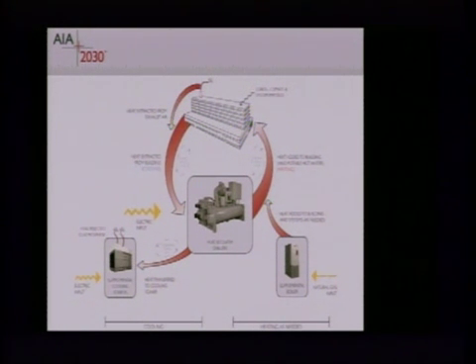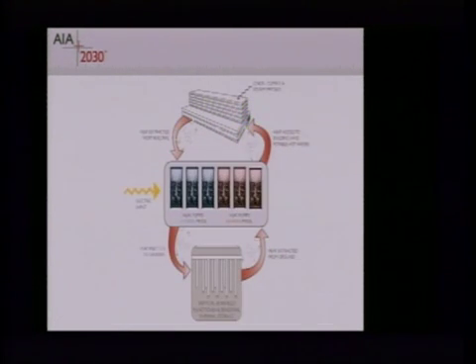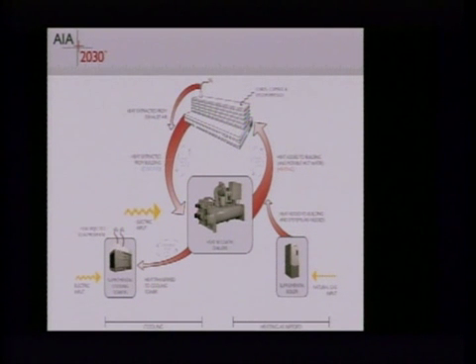And remember, these are mechanical engineers talking to architects commonly who may or may not have a very good idea of baseline systems in a building. This is the baseline most efficient system that we would look at, which is what we call heat recovery chillers. In a big building, there's heating and cooling commonly going on simultaneously. If you look at this diagram, a big building, this is a hospital, there's a cooling side and a heating side. Instead of having a chiller and a boiler that's doing all the chilling or all the heating, now we have a chiller that we're recovering the heat of and bringing that heat back into the building for reheat or heating in certain areas that don't need cooling.